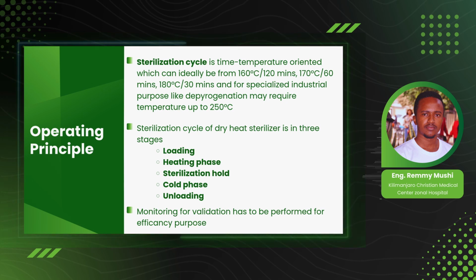And there is a sterilization hold. The sterilization hold is a period where the temperature inside the chamber is held at the same degree. This means that even if there is a fluctuation of temperature inside, it is going to be very minor, because the target here is to ensure that the temperature, presuming it is 170 degrees, is maintained for a specific period of time, in order to ensure that the load inside is completely sterile at the end of this sterilization hold.